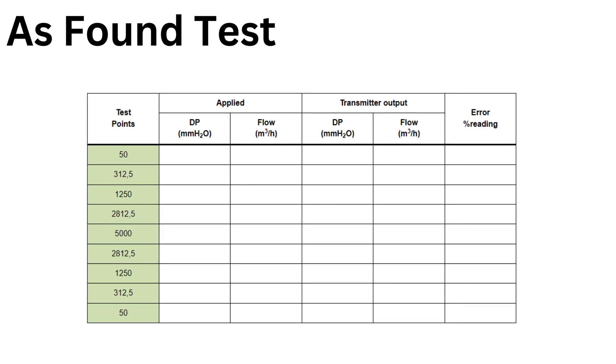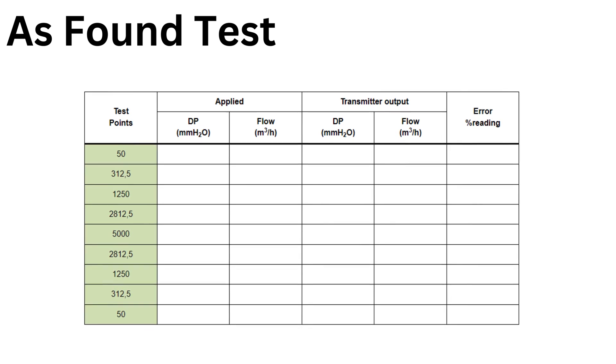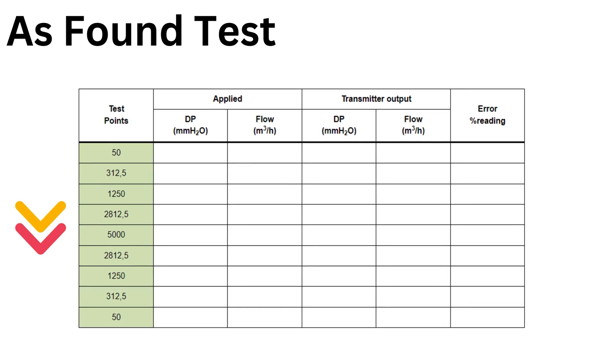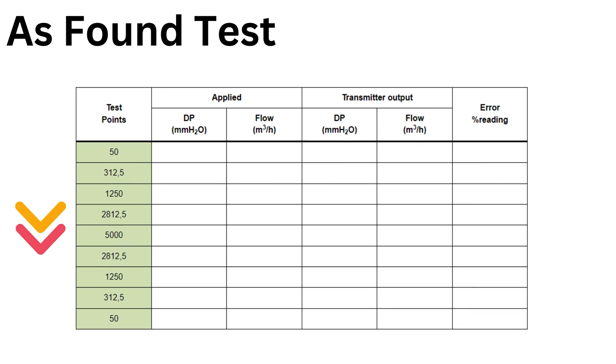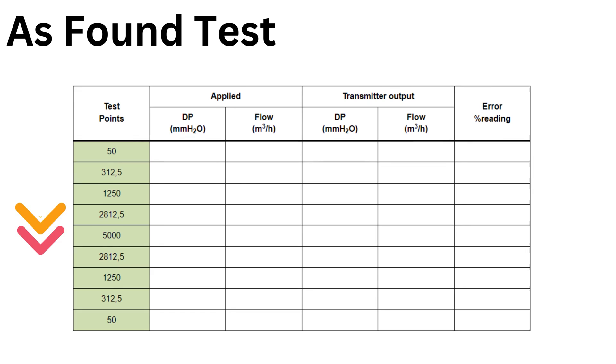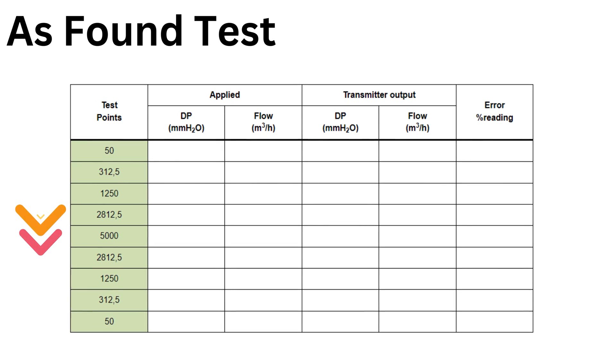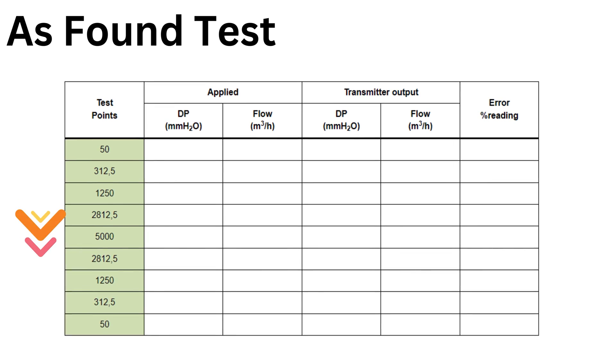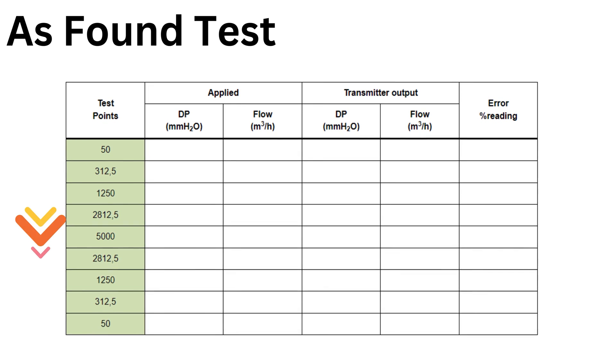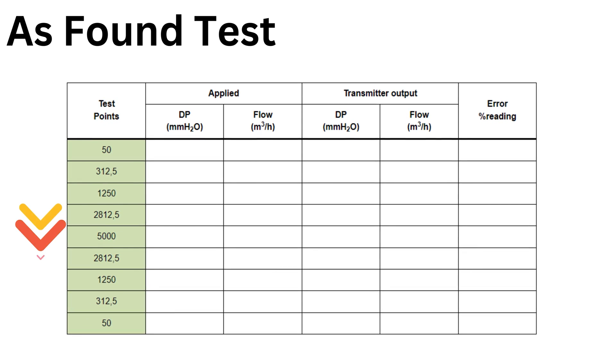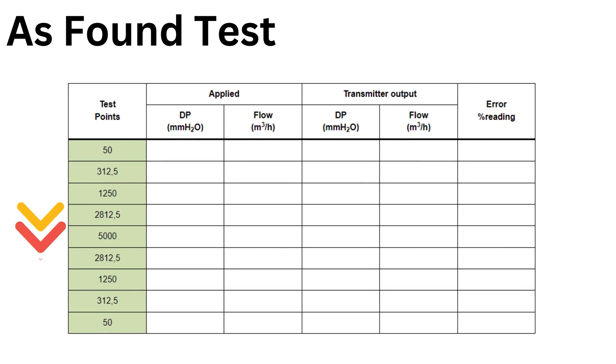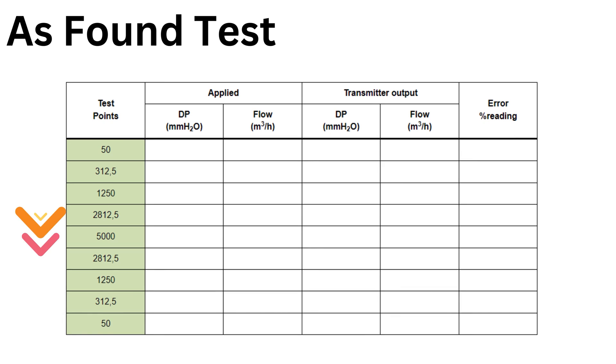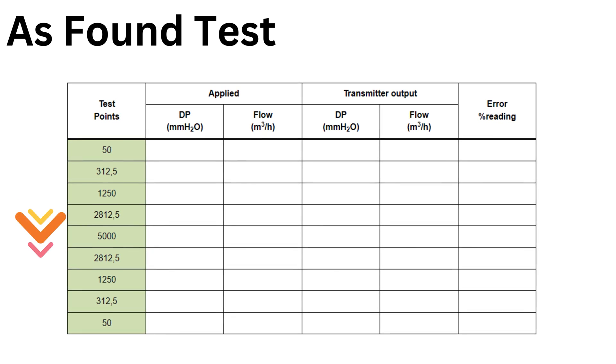We have filled in our test points based on a DP transmitter with square root extraction. You can see that our test points are going in ascending order from minimum to maximum value and then in descending order back to minimum. This is important because the results can be different for the same test point when approached from below or from above. So be very careful when approaching a test point not to overshoot it because if you have to come down again it will not give you the same result.